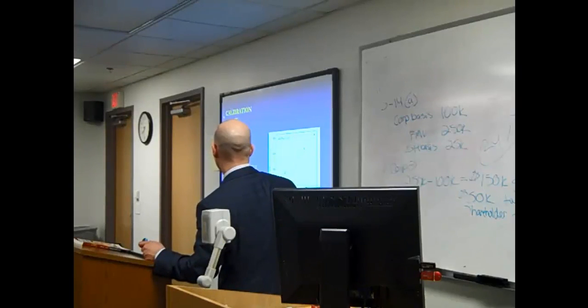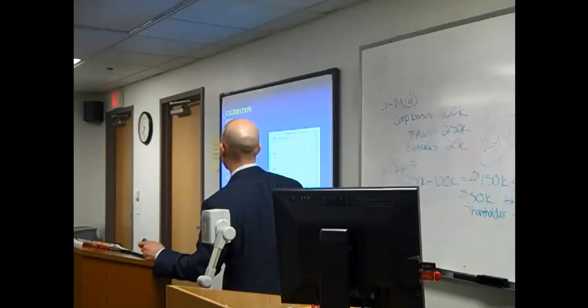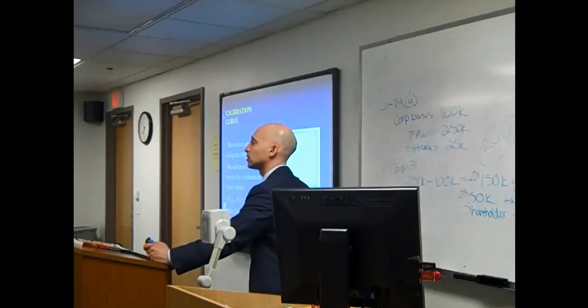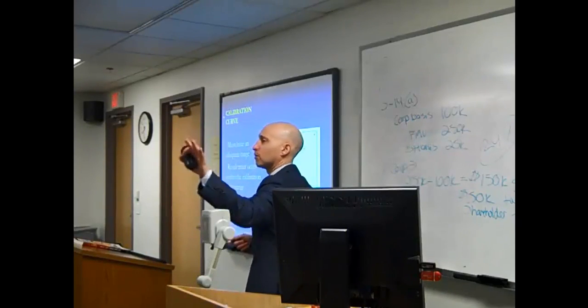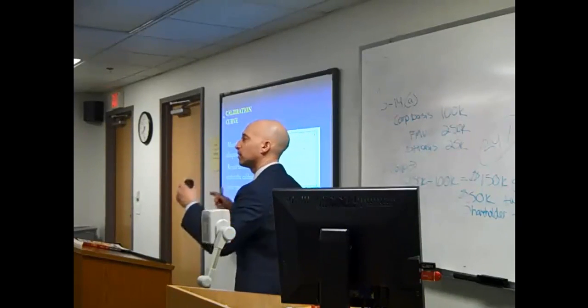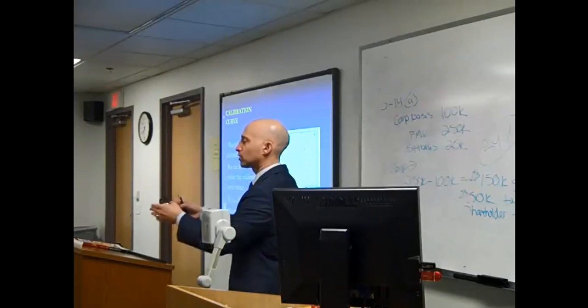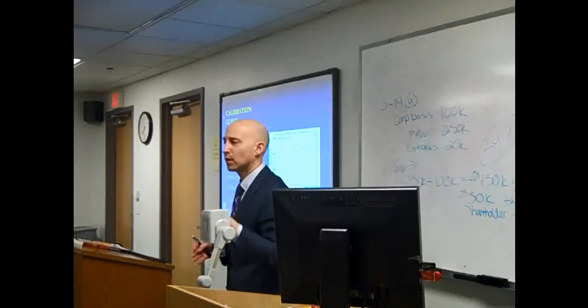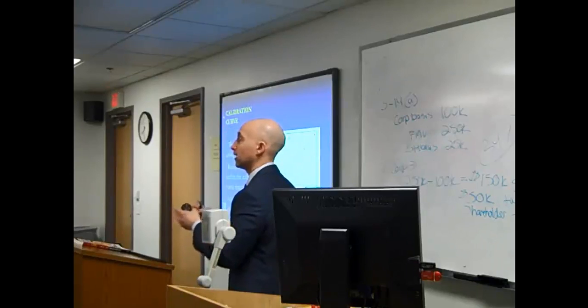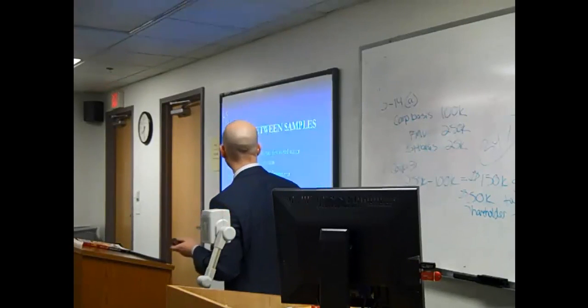And again, the calibration curve should be done before each run. You don't use a historical curve. So you don't go back to the one you did a week ago and say, all right, well, computer, let's utilize that curve from a week ago to quantitate today. No, you've got to do it each time before the run.